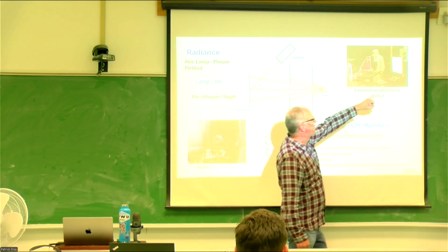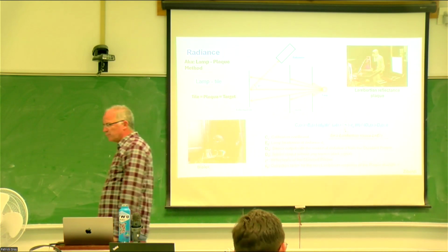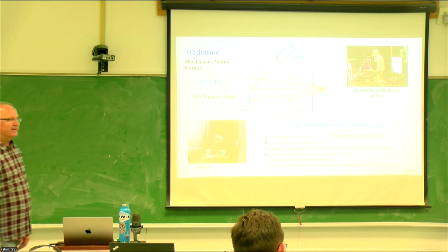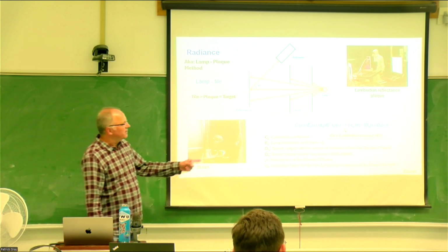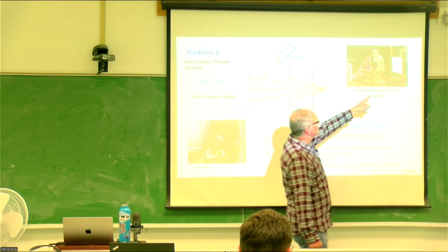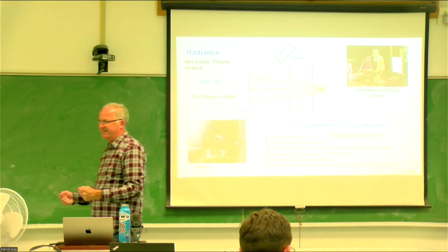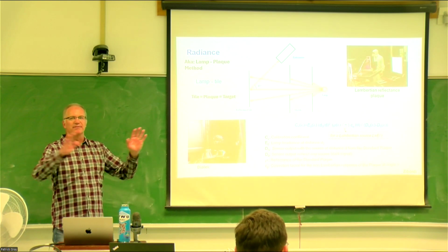This material, Spectralon, is just as bad, if not worse, than the FEL, in that it can get stained and it can age. It's really difficult to mount this thing in a fixture without touching the white, because if you touch it, you've changed the entire reflectance properties.